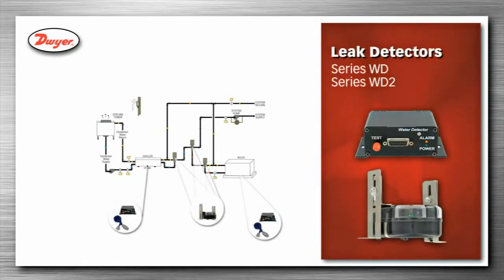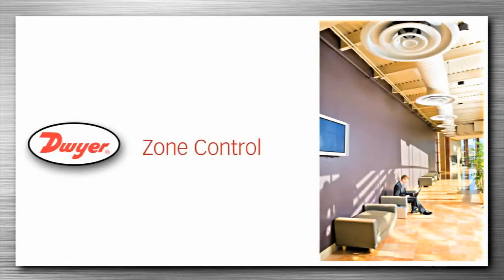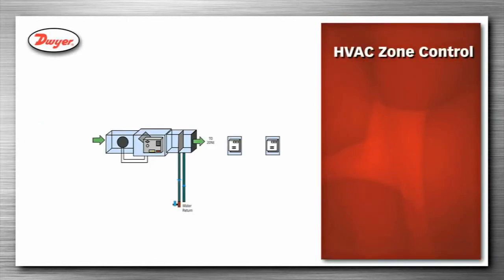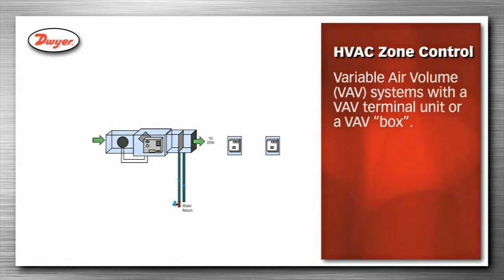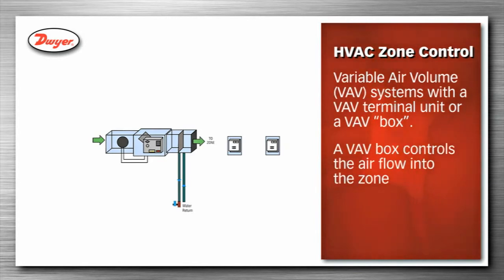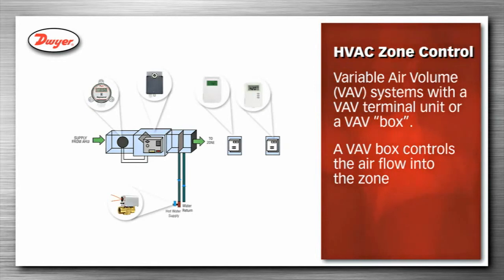Series WD and WD2 leak detectors are used to detect leaks of fluids around equipment and valves or to detect full drip pans. Zone control. Buildings are often broken down into zones for better control of the HVAC system. These zones can have variable air volume, VAV systems, with a VAV terminal unit or VAV box. A VAV box controls the airflow into the zone, thereby controlling the environment of the zone.